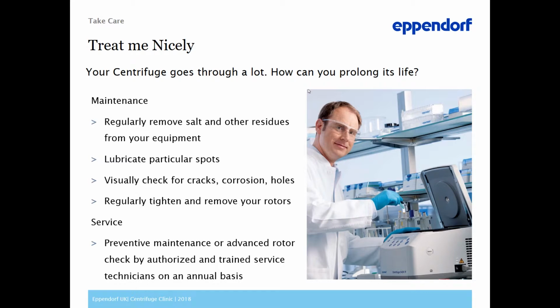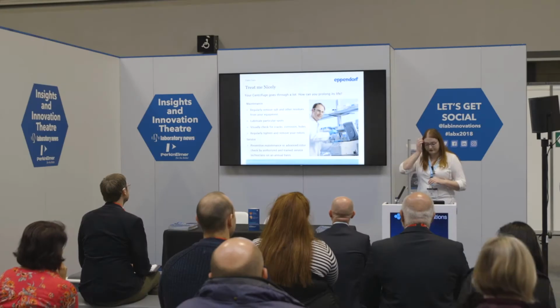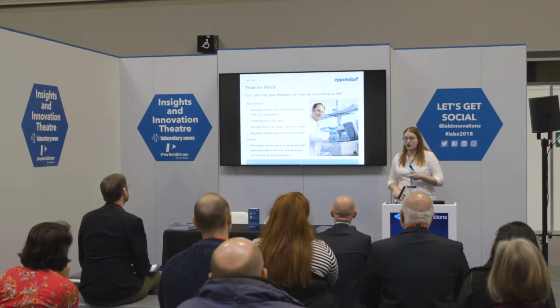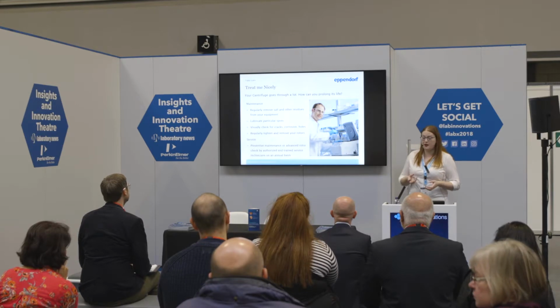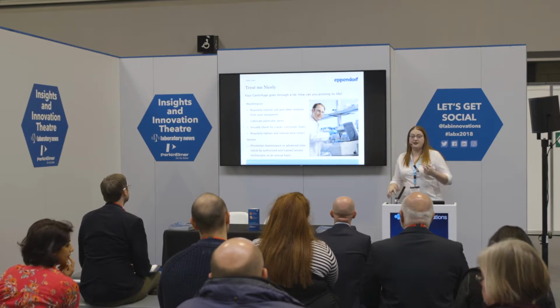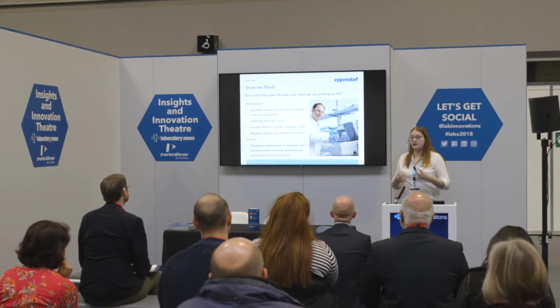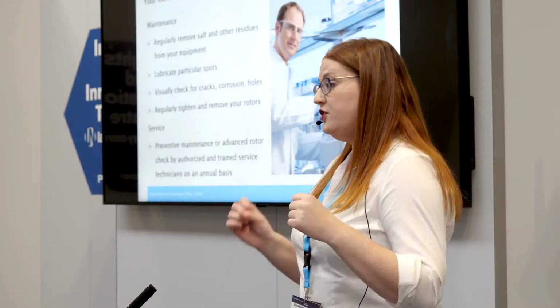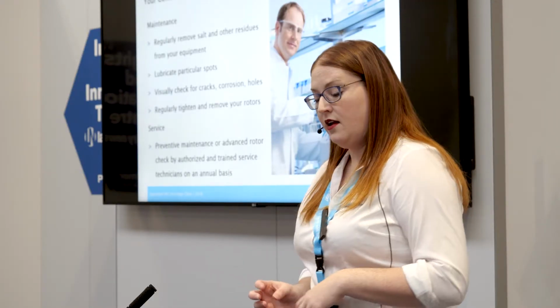You need to remove things like salt and other residues because they're just going to corrode your rotors, right? There's also particular places you should lubricate so you don't get metal grinding on metal. And you should also actively look for things like the corrosion and the cracks and the holes, because as soon as you start to get them, your centrifuge isn't safe anymore.